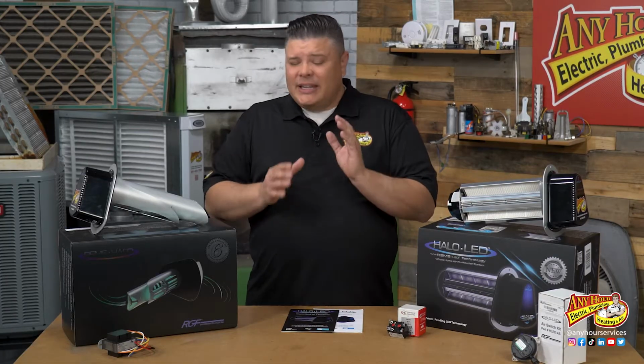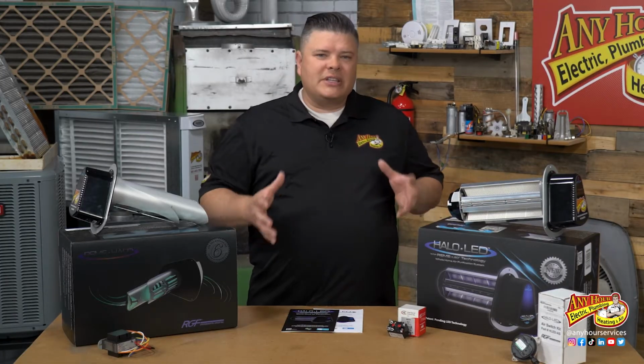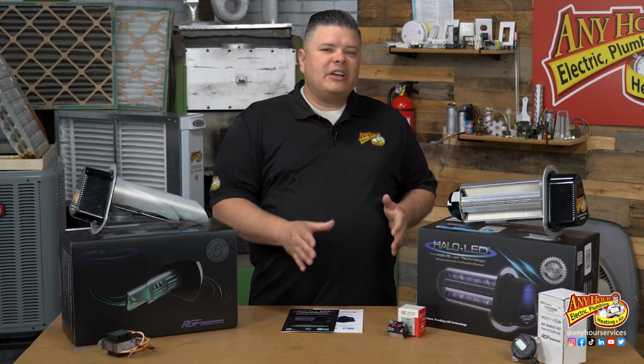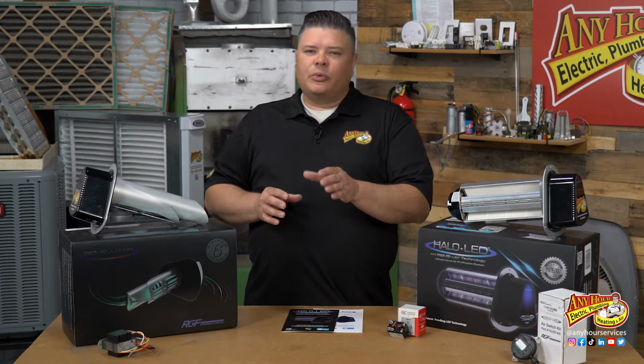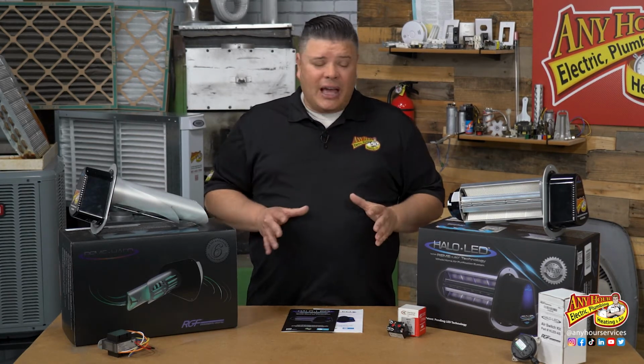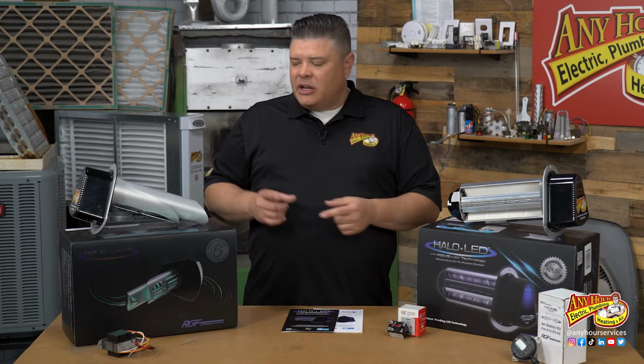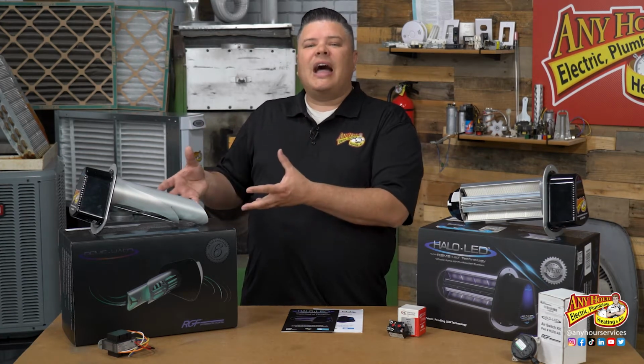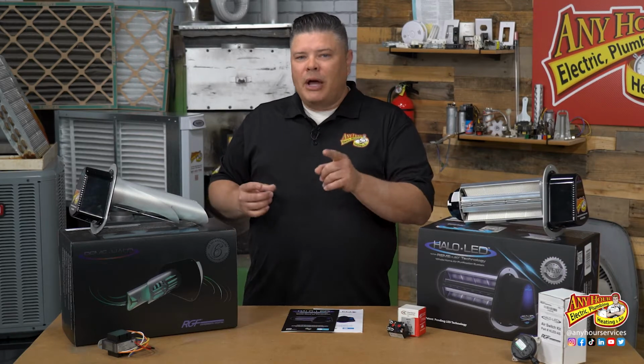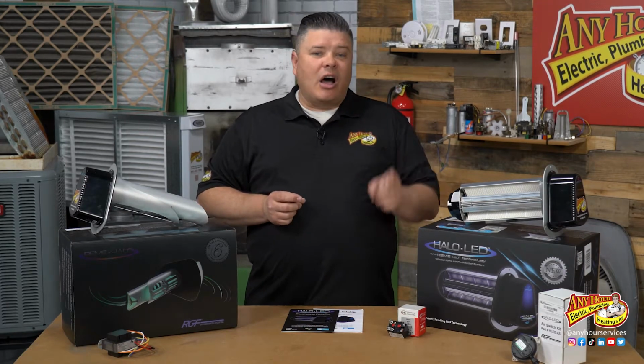Now, with the Halo LED needing to cycle on and off in order for it to last as long as it can, if you have a customer that insists they're going to run the fan in the on position all the time, don't install the Halo LED. Just install the Reme Halo. That's what it was designed to do, stay on all the time. But as long as the thermostat can be set to auto or circulate, you shouldn't have a problem.